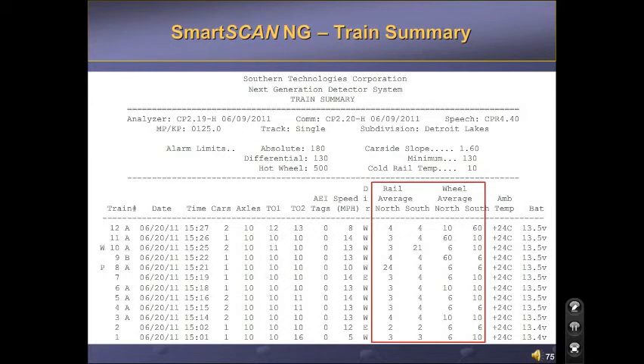The same heat average is true for the hot wheel scanners. These temperatures should be within 10 degrees of each other. If they are not, alignment and calibration should be checked. Make sure to switch the red filter for the black filter in the hot wheel scanner before calibration. Always replace the red filter in the hot wheel scanner before leaving the location.